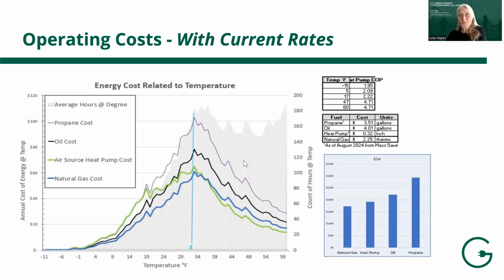Again, we have the same weather data, that's the gray screen here, but we've added different fuel types. Purple for propane, black for oil, blue for gas, and green for air source heat pump. And you see for the majority of the winter, the air source heat pump is going to be the most cost-effective of these 3 options. But as we get into the colder temperatures, gas can be more efficient, and in the really cold temperatures, oil, even propane can be as efficient.